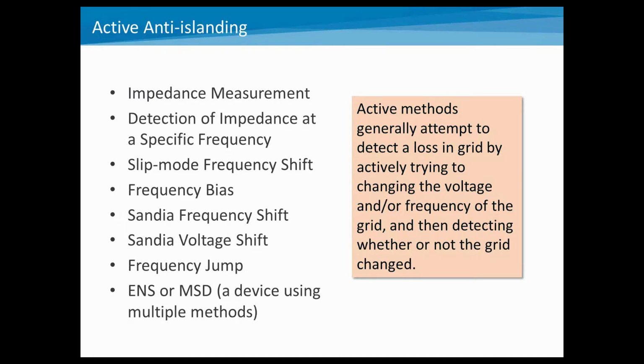But active anti-islanding techniques in general are trying to create a disturbance. When it moves into an islanded mode, it's actually able to move voltage and frequency, and then typically will push faster until it pushes outside those trip windows.